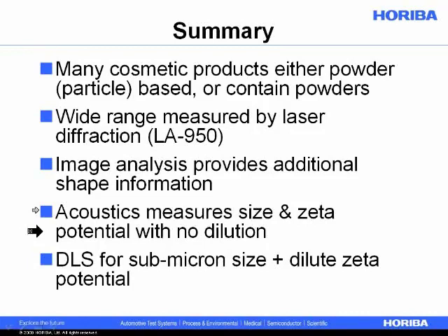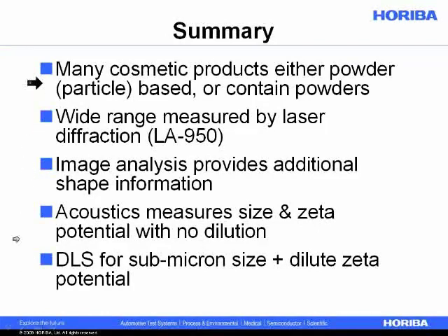We started by looking at powders and how they can be measured, and a wide range of them could just be measured using a single laser diffraction instrument, the LA-950. If you want shape information, we might use image analysis to get the shape of glitter flakes. We can use acoustics to measure both the size and zeta potential, with the additional benefit that there is no dilution with our measurements. If we're doing measurements all below a micron, we can use dynamic light scattering, which can be used for particle size and zeta potential of dilute systems.